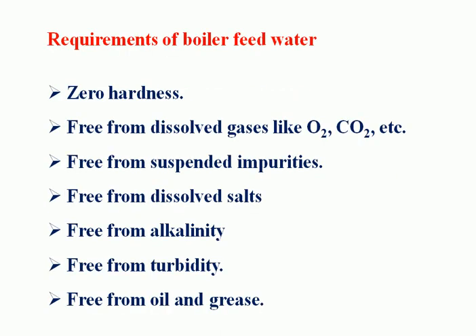What are the requirements of boiler feed water? The boiler feed water should be free from hardness. Hardness refers to unwanted dissolved salts like calcium and magnesium salts present in the water. It should be free from dissolved gases like oxygen and carbon dioxide, and free from suspended impurities, dissolved salts, alkalinity, turbidity, and oil and grease.